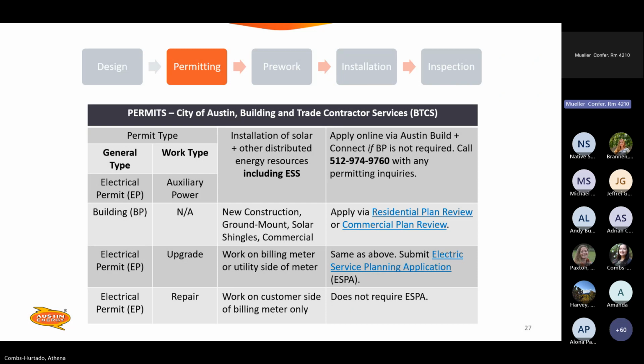Upgrades is when you're working on the billing meter or the utility side of the meter. Repairs is work on the customer side of the billing meter. So if you're installing a new main panel but the existing revenue meter can stay, that would be work done under a repair electrical permit, and it does not require an ESPA, which is for new services. If you are replacing the revenue meter can, then you will need to submit an ESPA under that upgrade permit, in addition to the DGPA under the auxiliary power. Batteries and energy storage systems can also be installed with the auxiliary power permit.